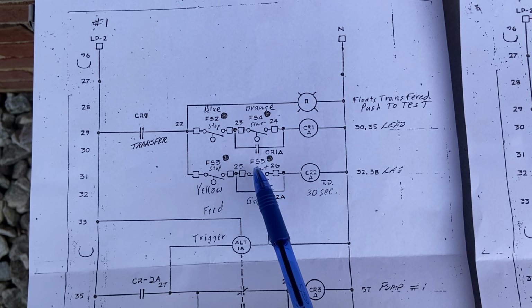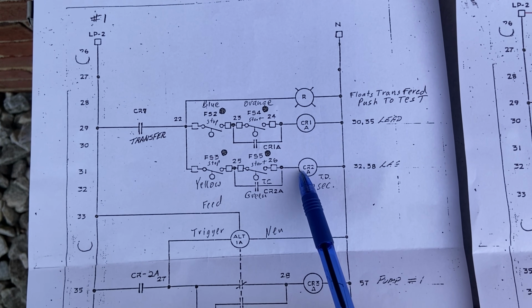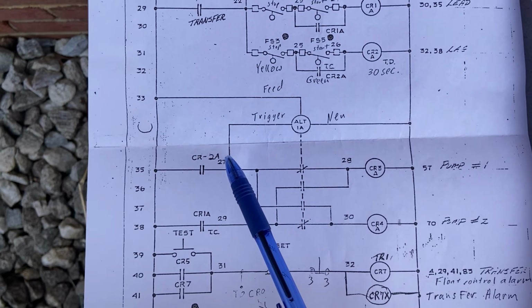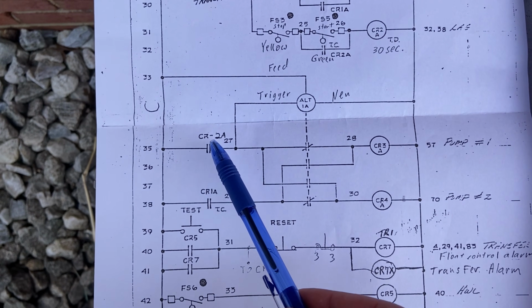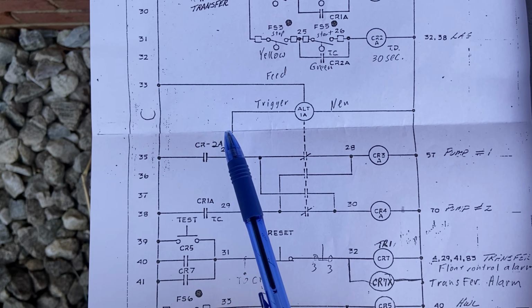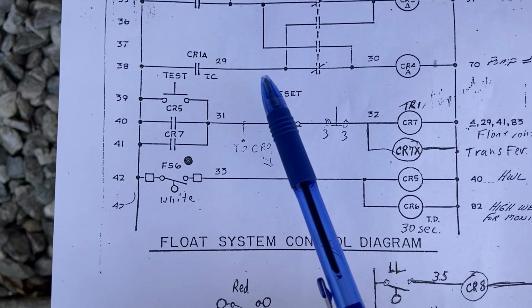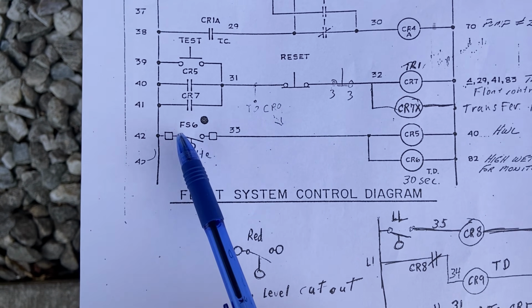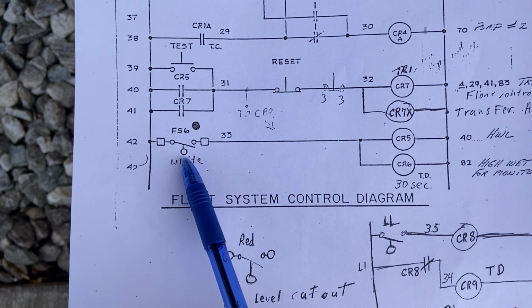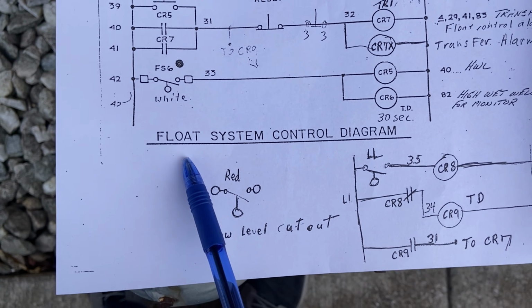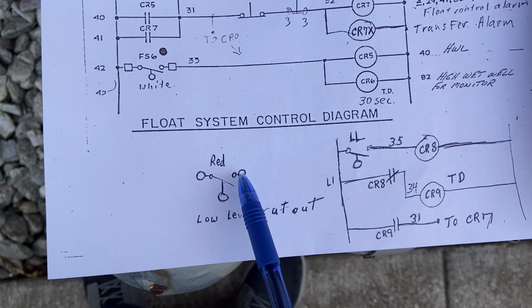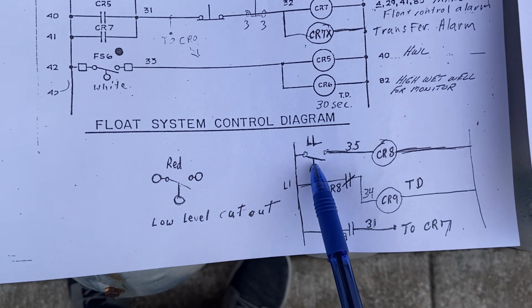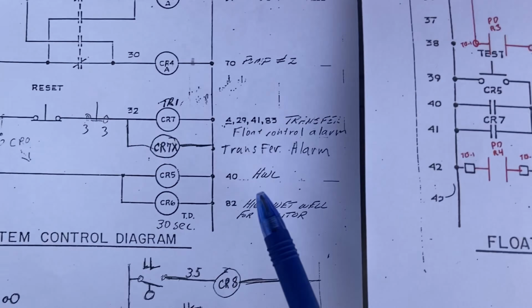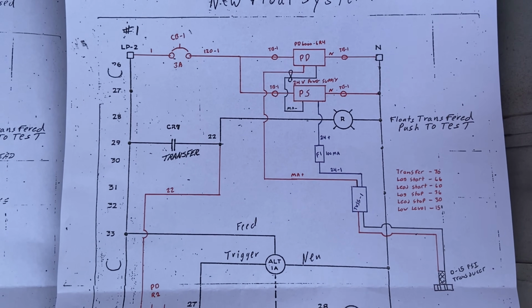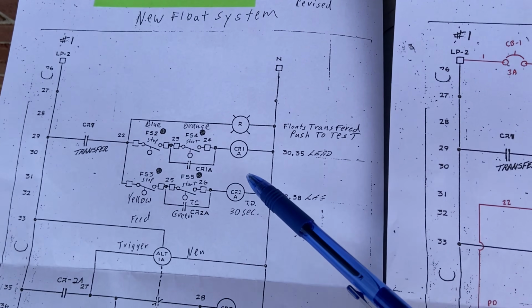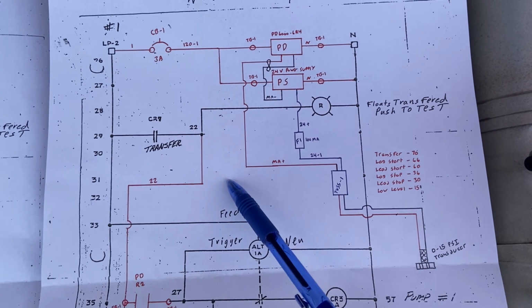now run normally. So if we look back at our diagram, I'm just showing you here all the things that got modified or removed. Obviously all the floats were removed, CR1 and 2A were also removed because we no longer need them, and those contacts going to the alternator were replaced with the contacts from the display. The transfer and low level float were also removed and replaced with contacts from the display, just like the lead and lag. So we went from 6 floats to a single transducer and a display with 4 relays, so definitely simplified things. Here is my modified diagram.